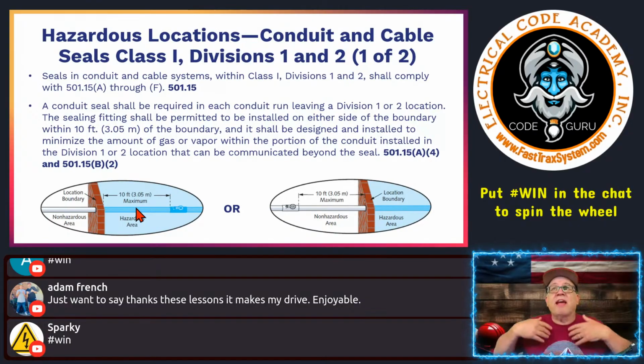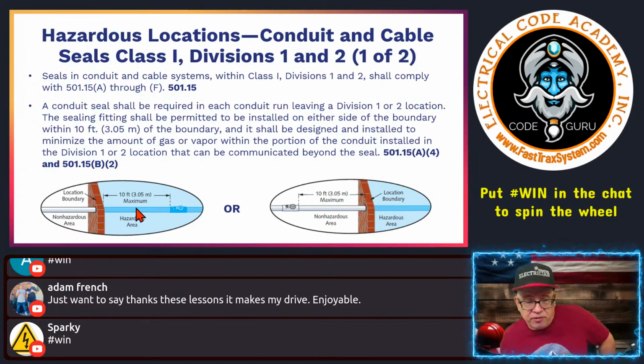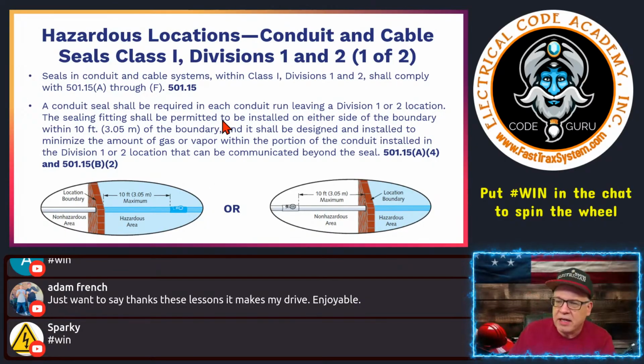And so now let's say, even though it's adjacent, it may have pressurization, it may have air exchanges, it may have something that takes it from a hazardous location. Even though it's adjacent, it turns it into a non-classified or unclassified or non-hazardous area. Now you have a raceway that might be passing from a hazardous location into this area that is not a hazardous location. Where do you put the seal? This one, I get a lot of people are confused about this one. All right, so here's what it says.